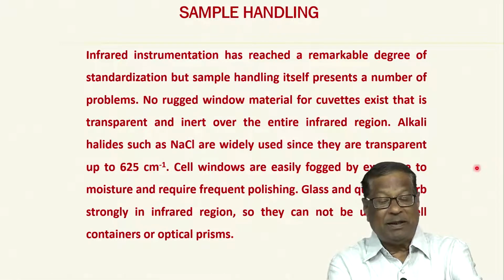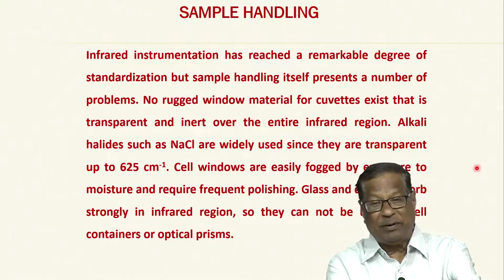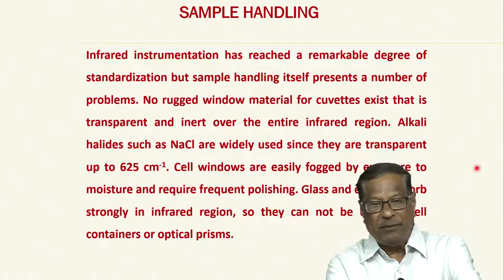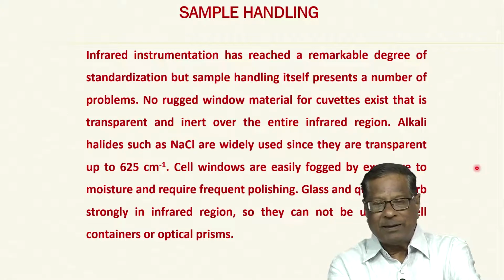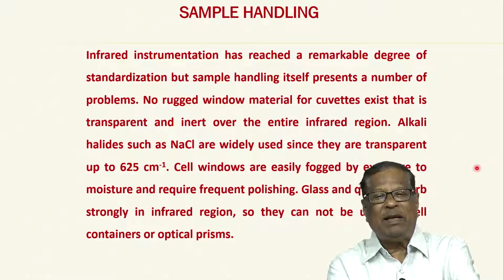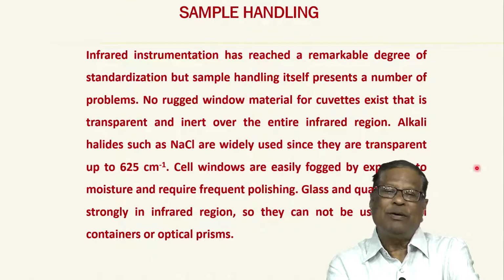For example, there is no rugged window material for cuvettes, just like in spectrophotometry. We have quartz for ultraviolet and glass or polystyrene cuvettes for the visible range. Like that, if I want to take an IR spectrum from 4000 to 200 or 10 centimeters inverse, I do not have a single cuvette which can be transparent at all these wavelengths.